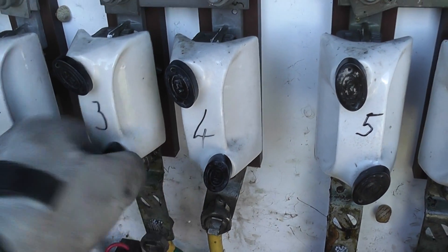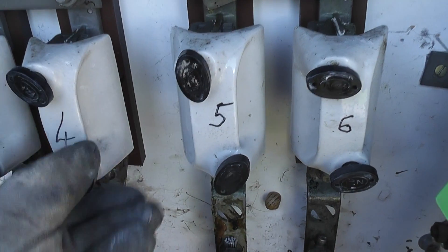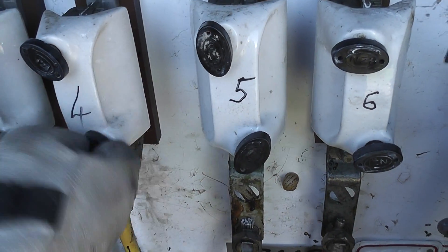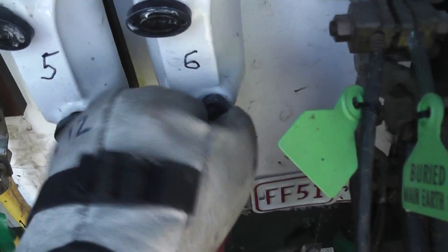It's important to do up all these screws on these fuses. If they're not — they're wedge connectors. They wedge like that. You can't see it, but they're wedging and if you don't do them up they'll push themselves out.